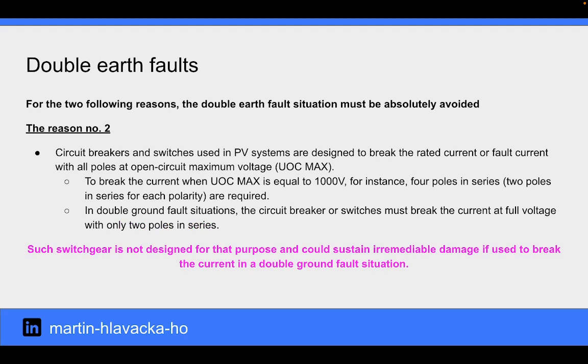Circuit breakers and switches used in PV systems are designed to break the rated current or fault current with all poles at open circuit maximum voltage. To break the current when open circuit maximum voltage is equal to 1000 volts, for instance, 4 poles in series are required. In double ground fault situations, the circuit breaker or switches must break the current at full voltage with only 2 poles in series. Such switchgear is not designed for that purpose and could sustain irremediable damage if used to break the current in a double ground fault situation.